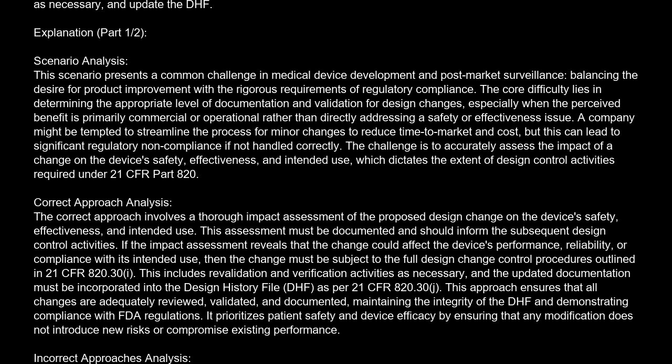Correct approach analysis. The correct approach involves a thorough impact assessment of the proposed design change on the device's safety, effectiveness, and intended use. This assessment must be documented and should inform the subsequent design control activities. If the impact assessment reveals that the change could affect the device's performance, reliability, or compliance with its intended use, then the change must be subject to the full design change control procedures outlined in 21 CFR 820.